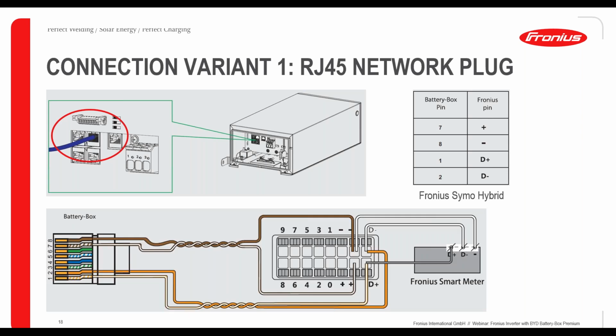In the next slide, you now see the battery box connection pin. So this is the Cat5 cable connected to the network connection of the battery box. And then we have, this is very important, twisted pair shield cables. So in this case, you see the D+ and D- connection coming from the Fronius Symo Hybrid. These cables must then be twisted to each other. So in this case, with the network cable, this is already done. And then you connect it to pin 1 and 2 of the battery box.